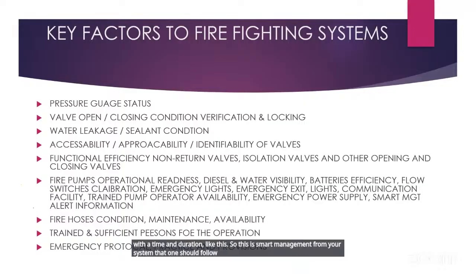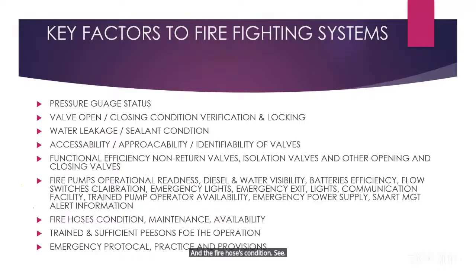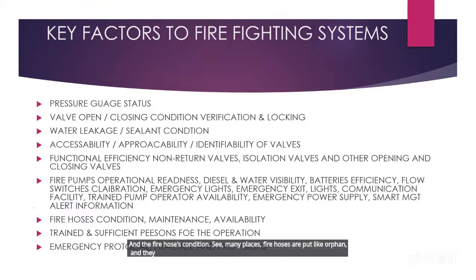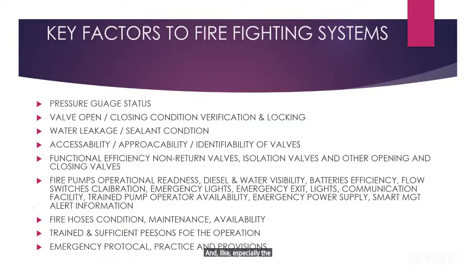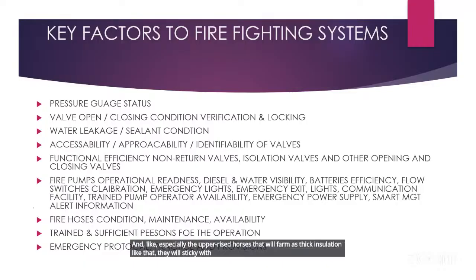And fire hoses condition. See, in many places fire hoses are put like orphans, and they don't give any care. They must be unrolled and rolled. When used, they must be dried, and the water should not be there. So change of hoses must be there. The same hose should not be kept at the same place for a year together, so that it will not deform its shape. Especially the rubberized hoses that form a thick insulation will stick to each other. So proper maintenance should be there, and recording should be done.